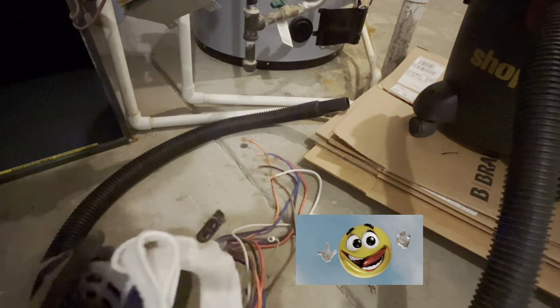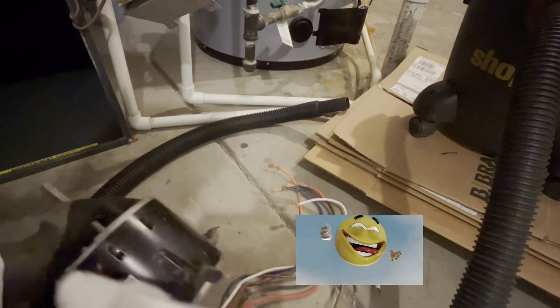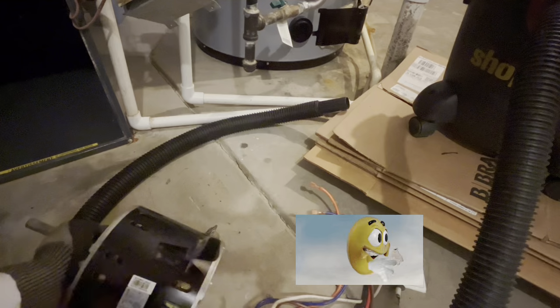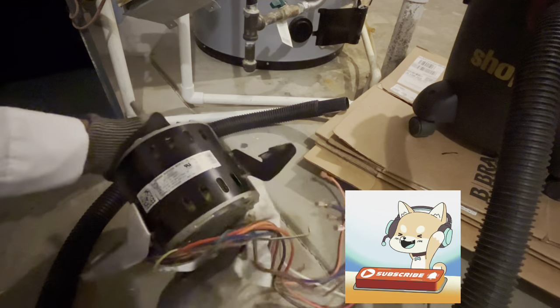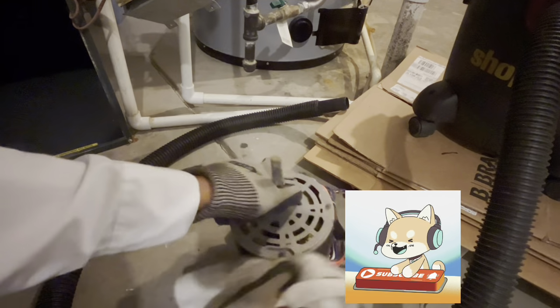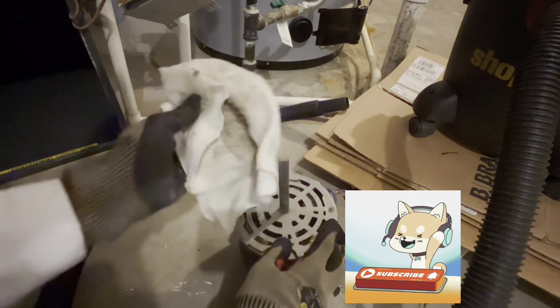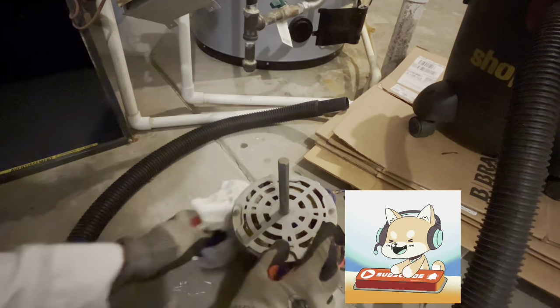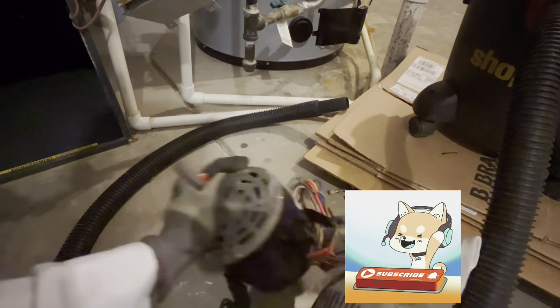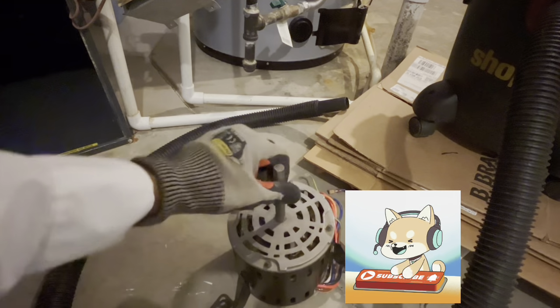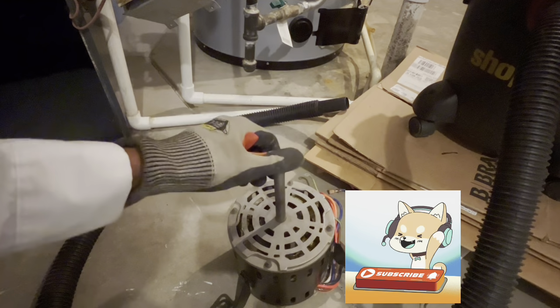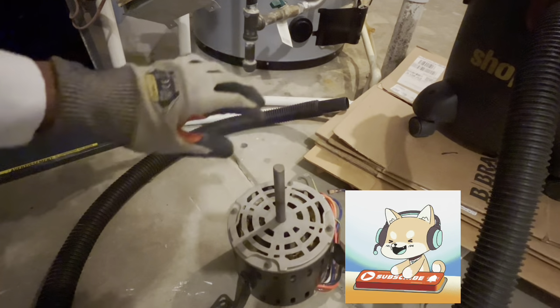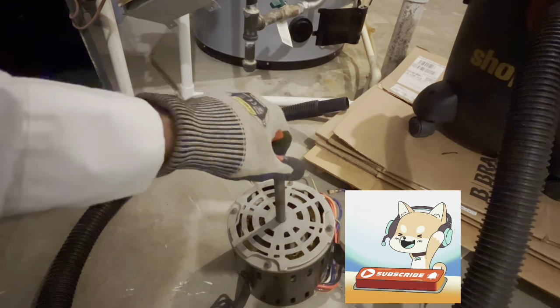From what I remember on this one, I think we caught it in good enough shape before all that dirt and debris caked it over, because it would have suffocated it, and basically it would have overheated that motor. Then the motor would have leaked oil, and then it would have seized up, and it would have ended up burning out the circuit board too, because now it's working harder than it should. It's using more power, then the circuit board starts burning out too. So it's kind of like an orchestra. Once one instrument is out of tune, the whole event sounds bad. So you have to keep everything in good working condition. I believe that shaft had a little bit of wobbliness.